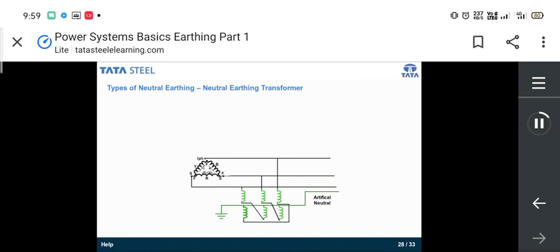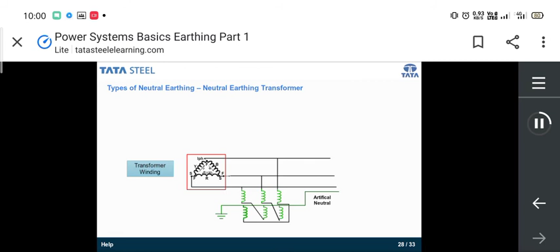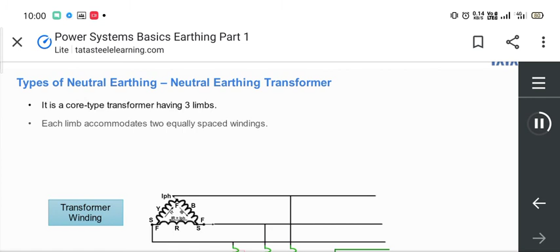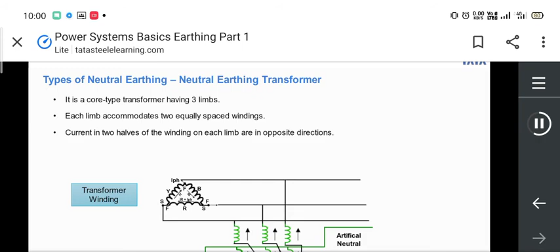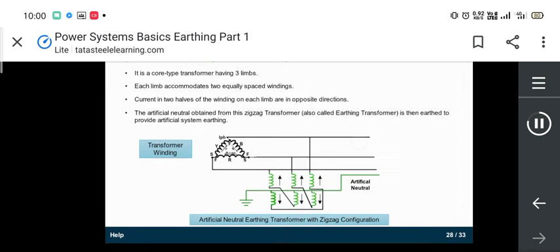Let us now learn about the features of artificial earthing. Here is the diagram of an earthing transformer with zigzag configuration. You can also see the transformer winding. It is a core type of transformer having 3 limbs where each limb accommodates 2 equally spaced windings. In this system, as you can see, the currents in the 2 halves of the winding on each limb are in opposite directions. The artificial neutral obtained from this zigzag transformer, also called an earthing transformer, is then earthed to provide artificial system earthing. Well, that was all about types of neutral earthing.